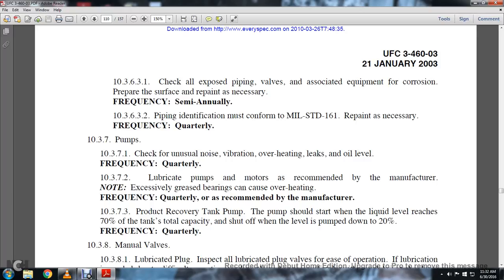10.3.7.3 Product recovery tank pump. The pump should start when the liquid level reaches 70% of the tank total capacity and shut off when the level is pumped down to 20%. Frequency quarterly.